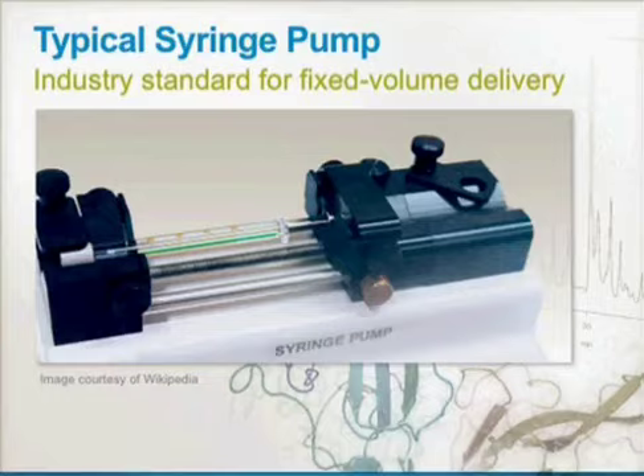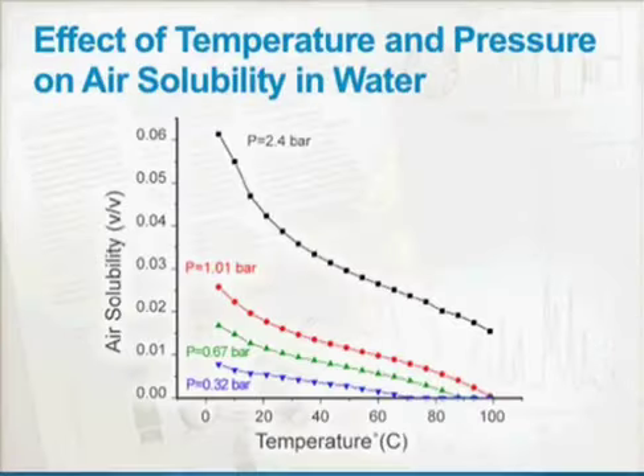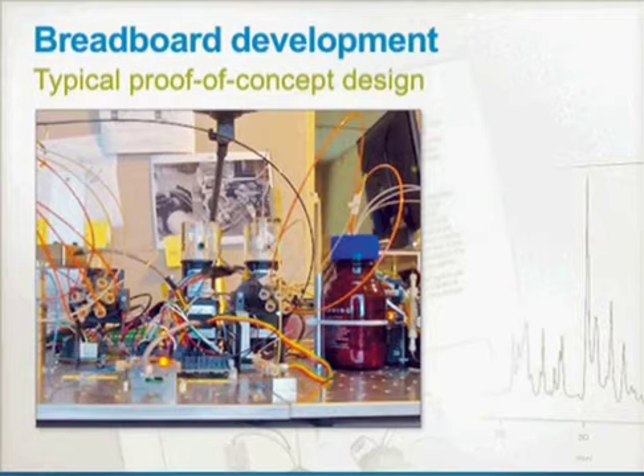Yeah, I think it's fair to say there are a lot of very good applications for syringe pumps, just not necessarily nanogradient work and not necessarily work where you have an outlet that varies in pressure or where air bubbles could become a problem for you. And so that was an issue for us too, right? The outgassing of the solvent when you drop things across a pressure drop like we did, or flow things through a pressure drop. That's what required us to also operate the digestion element at an elevated pressure as well, so we could control that. And that was part of getting that extra level of performance.